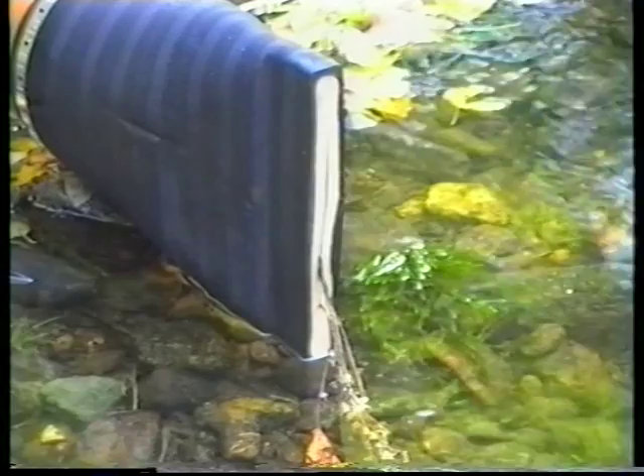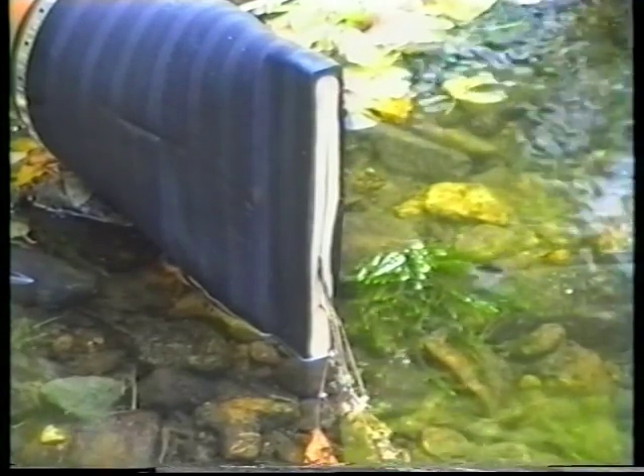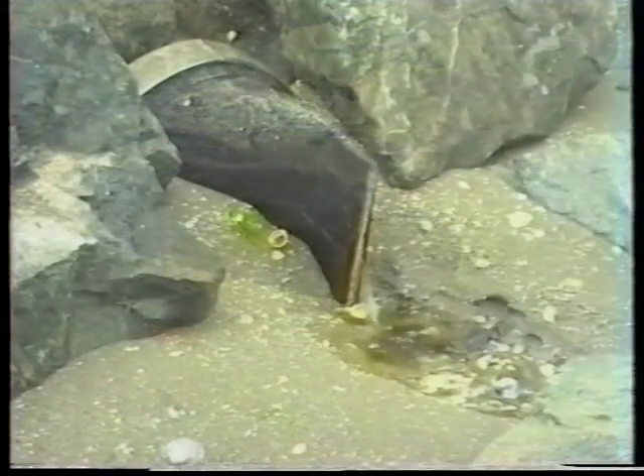The duckbill design responds instantly to rapid flow reversal, and the cushioning action of the rubber eliminates noise and excess pressure on pipes. Because there are no metal or mechanical parts, the Tideflex check valve does not break, warp or freeze. Its flexible rubber construction will accommodate all types of debris, but still form a tight seal around it when water levels rise. As very little internal pressure is needed to open them, silt and sand buildup does not interfere with drainage.